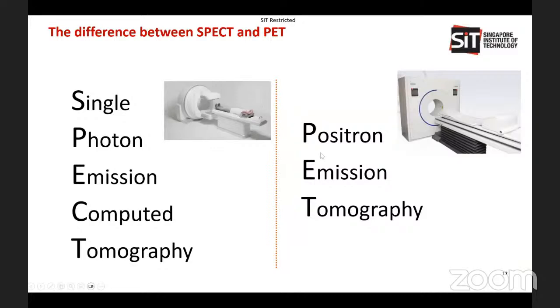And positron is the emission of the positron when it meets an electron, then there will be annihilation, and there will be two gamma photons in opposite directions, and this detector will detect to measure exactly the position of the annihilation event, suggesting the location of the distribution uptake. And radiographers often have to do QC on this PET system.